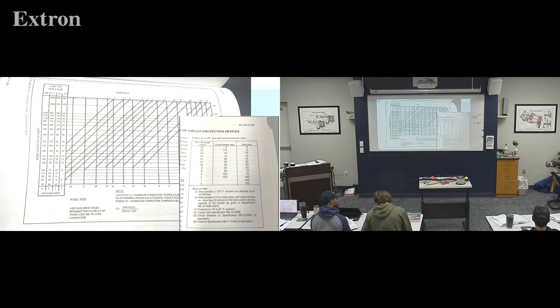The way a circuit breaker works is you have an amp draw going through it. There's a set resistance inside, and it warms it up. If it warms up too much - higher amperage means more warming - it trips. So circuit breakers have a bit of a delay effect built in, and they tend to be a little more accurate because they're more engineered.